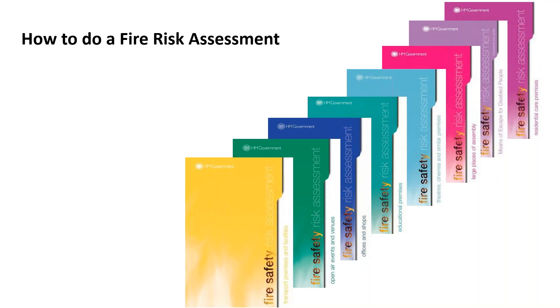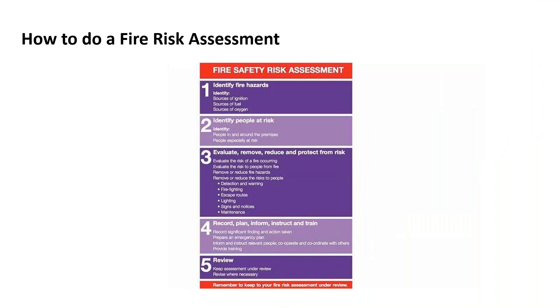Within those guides there are five fundamental steps, which are very health-and-safety-based methods of conducting a fire risk assessment. Step one is identifying fire hazards — looking at sources of ignition, sources of fuel, and sources of oxygen. PAS 79, interestingly, doesn't even mention sources of oxygen within the process of identifying fire hazards, merely because we understand that atmospheric oxygen is obviously going to contribute to fire. For standard risk assessment you wouldn't really be considering anything other than atmospheric conditions.